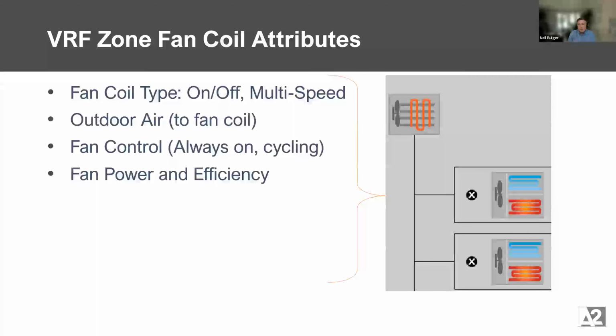There's now these multi-speed fans that I'm a big fan of, where you can use that fan and then say, what are my speeds? Or do I have a continuously changing speed? Can I use a curve like I would with a VFD and be at any speed that's needed? And that gives a little bit more control and a little bit more realistic performance that we'll see to how much energy it takes to run the heating and cooling system.